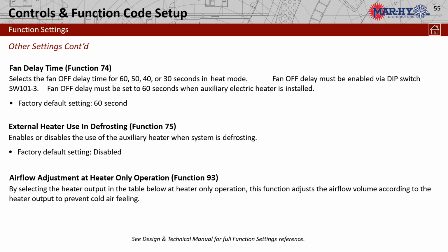Function 75, external heaters and defrost. So if you have strip heaters, you might as well use this function. Enable this function. So what that'll do is during defrost mode, like our typical equipment, the indoor fan will continue to run. The strip heaters will come on during the defrost mode to temper that air, so hopefully it's neutral. The unit will absorb more heat to actually make it a quicker defrost for the outdoor unit, because it still absorbs heat in that coil, and that indoor coil, and it helps to defrost the outdoor coil with the heat being absorbed. It makes for a quicker defrost. So that's something we would enable if we have strip heat.